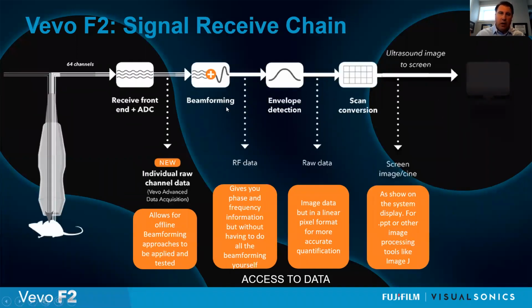Looking at the receive path, we can see that as the signals come in on the front end of the electronics through the analog digital converter, the individual raw channel data can now be acquired. This is the new element on the Vevo F2 that was not available on previous generations of our system. We still then do the beamforming, envelope detection, scan conversion to ultimately produce an image. There are various data points still available as have been on our previous systems, some of the other platforms that I showed you earlier. So we can get beamformed RF data, we can get raw data, which is an envelope detected version. We can get all of the various images and cine loops off of the system. All of that's still available. What's new here is really the ability to get down to the individual channel data, which is very, very important if you are experimenting with beamform techniques, plane wave imaging approaches.